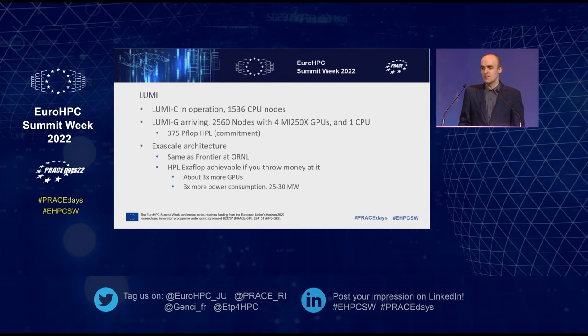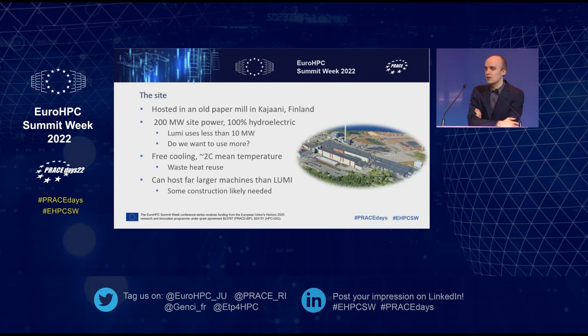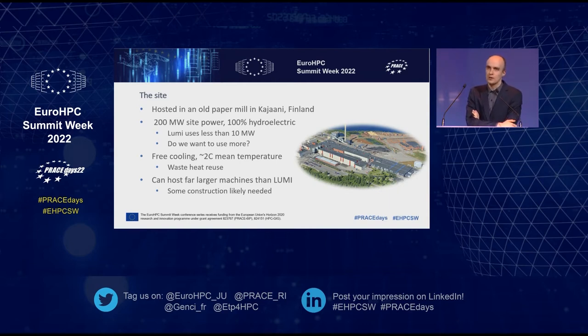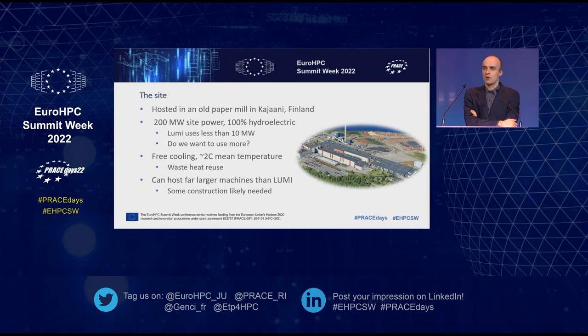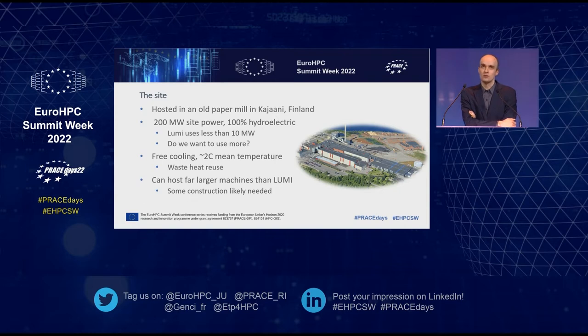The question then is, if we want to scale up, whether 30 megawatts for an exaflop is sensible. Talking on the power consumption brings me to the site where we're hosting it. It's hosted in an old paper mill in Kajaani, Finland, in the hall where the paper machine used to be. The site has 200 megawatts of power available, all hydroelectric, so zero CO2 emissions. Of that, LUMI uses less than 10 megawatts. It's fairly far north, so you can get away with free cooling most of the year — about two degrees Celsius mean temperature year-round.